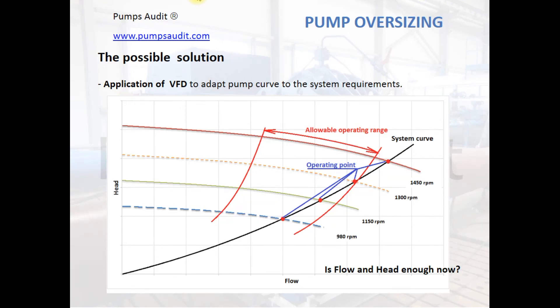The application of a VFD allows the pump curve to be changed. As shown in the diagram, the operating point moves and gets inside the allowable operating range at different speeds. However, it is necessary to confirm that the parameters at lower speed satisfy the system requirements. Also keep in mind that variable speed control may not be very effective for systems with high static head.